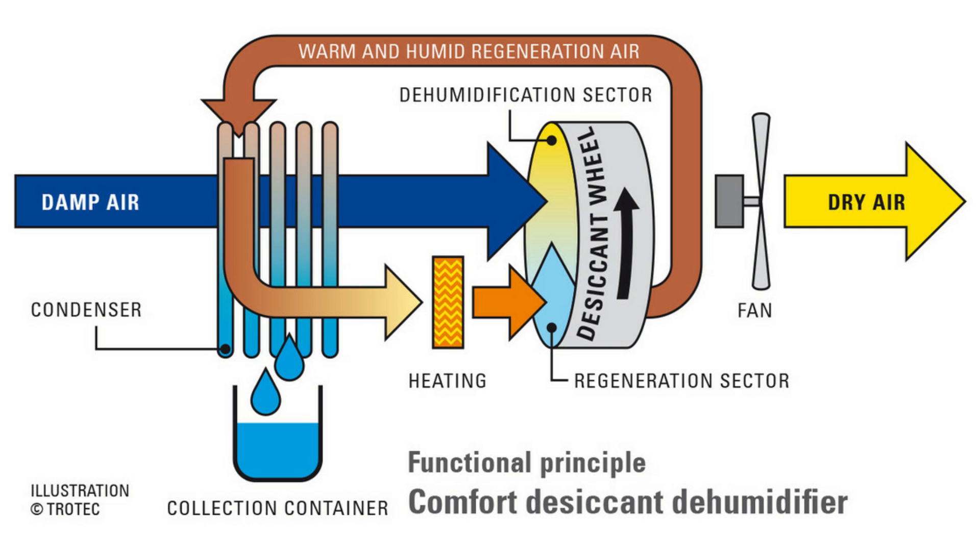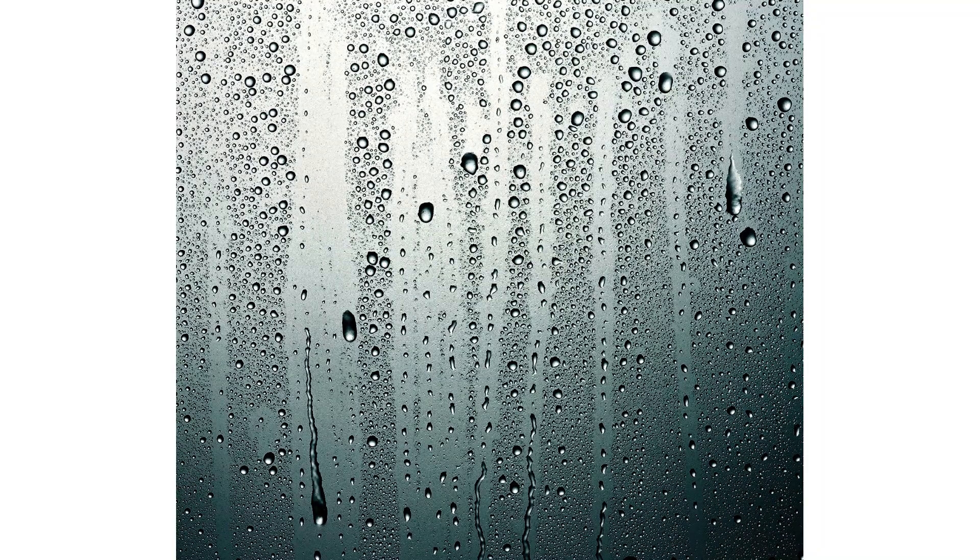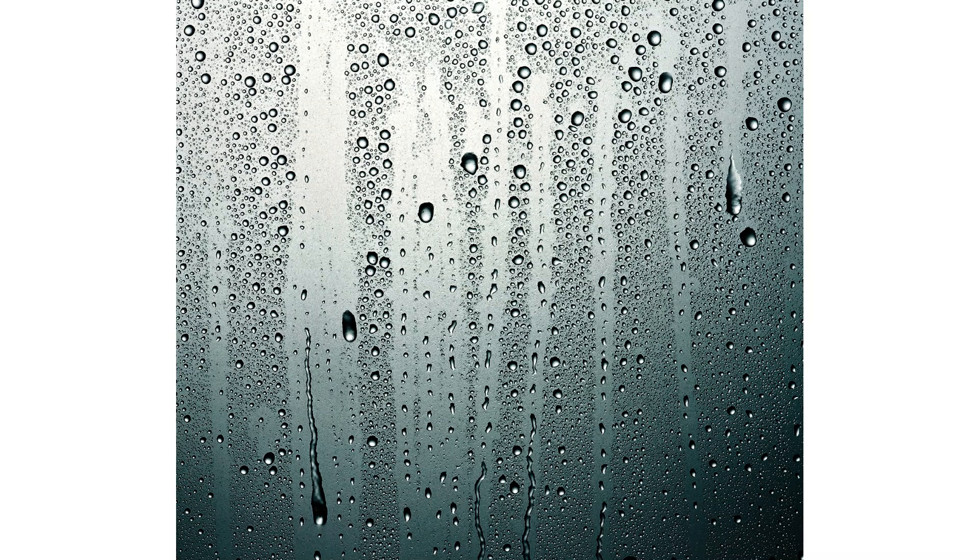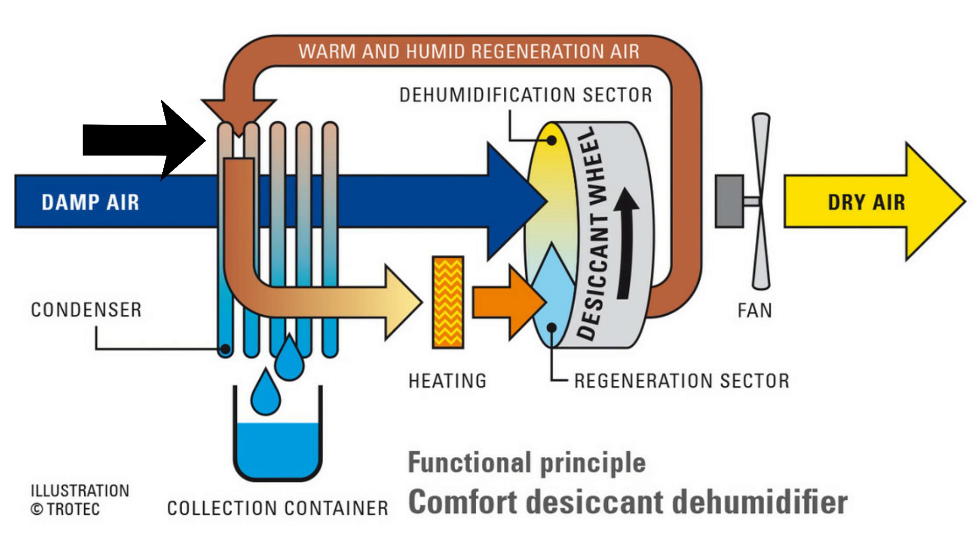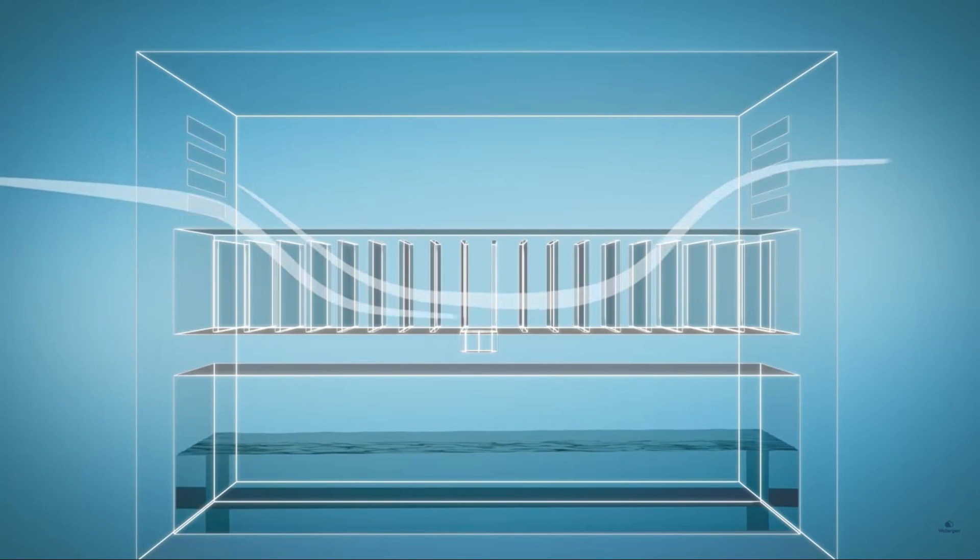The hot air becomes relatively more saturated with water. Note that water absorption capacity of air rises exponentially with the rise in temperature. Similarly, water retention capacity also drops dramatically with drop in temperature. So that relatively moist hot air is then passed through an air-cooled condenser. The drop in temperature of the hot moist air results in condensation and collection of water.